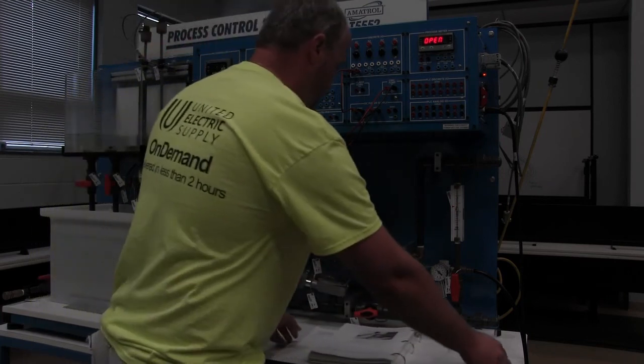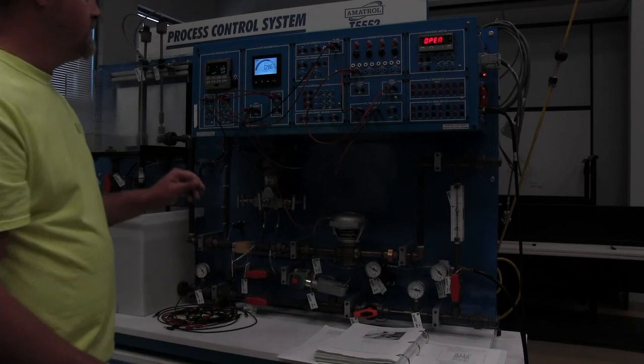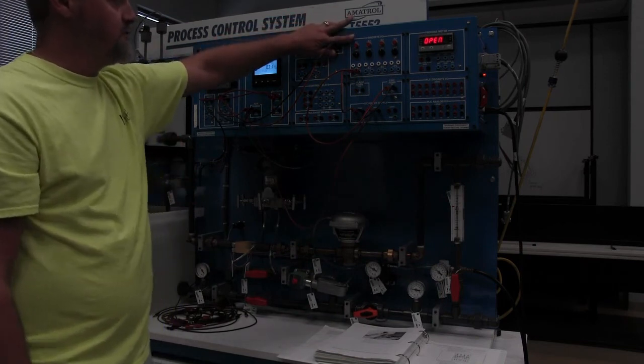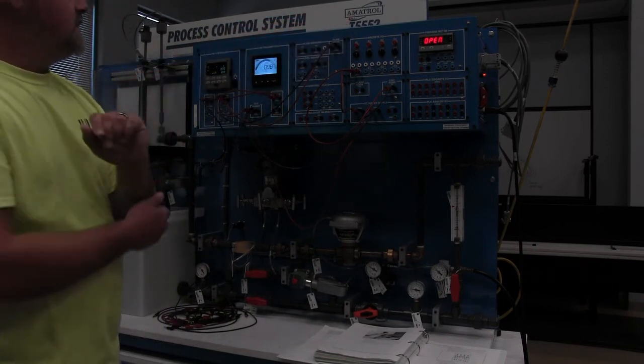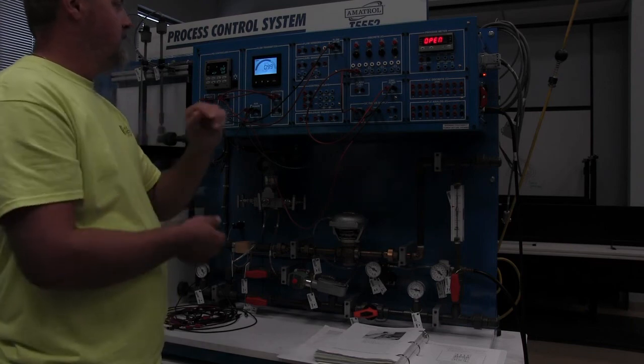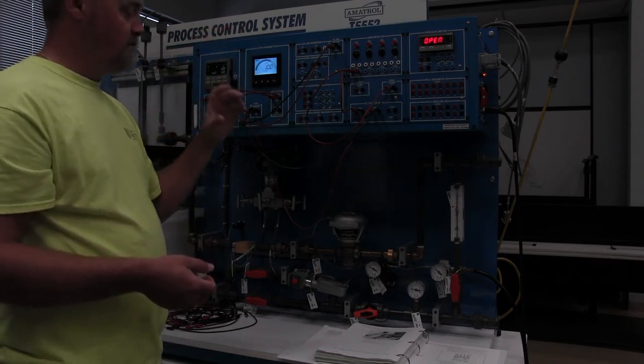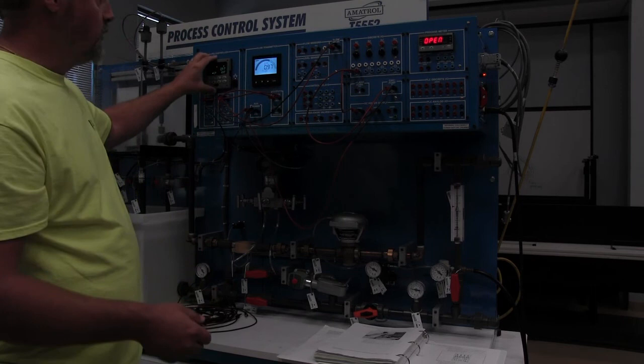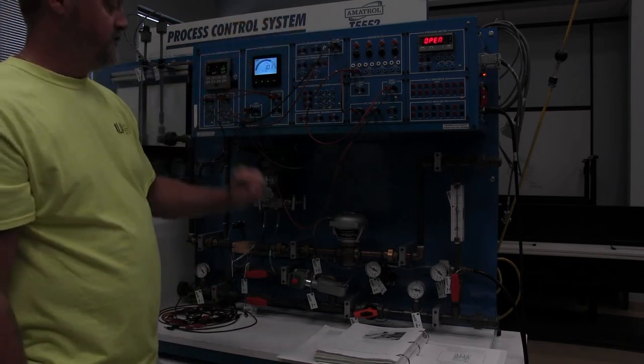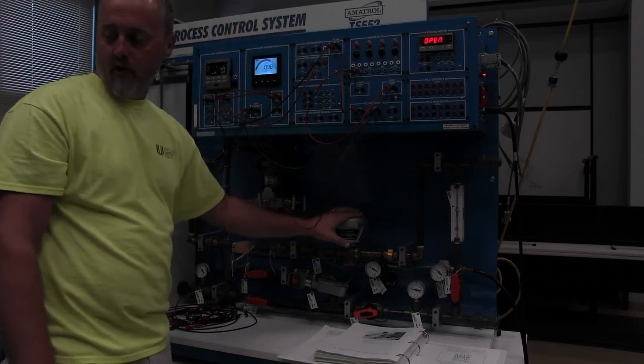Going to go over a few things here. We're going to tie into this loop so we can see on a 4 to 20 meter the 4 to 20 milliamp signal that this controller is outputting to this flow valve to tell it whether to open or close more.